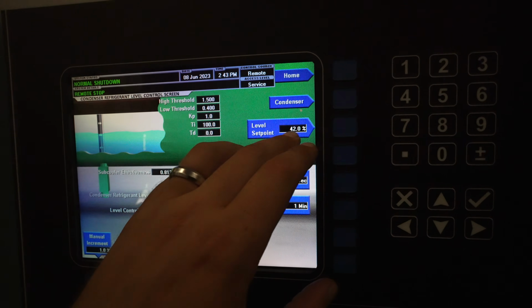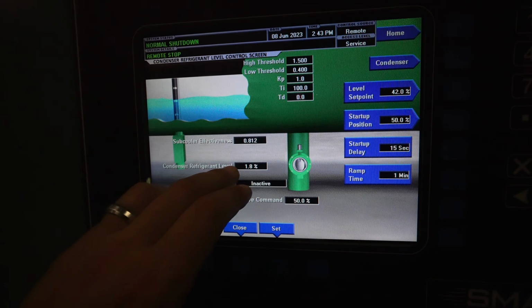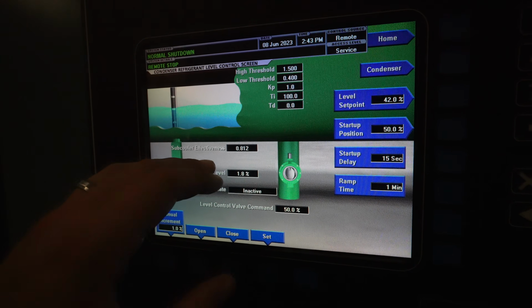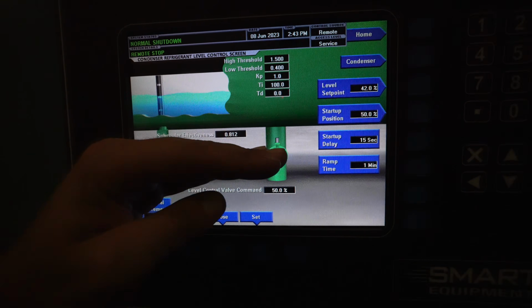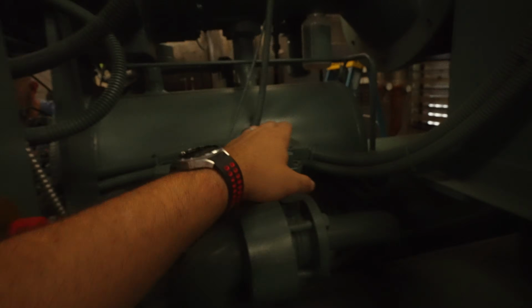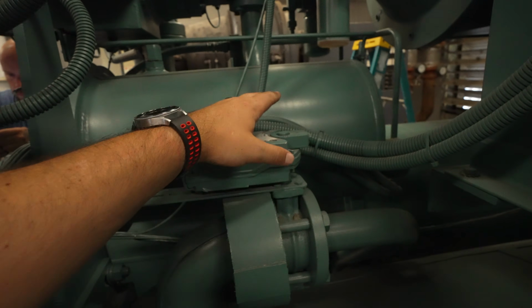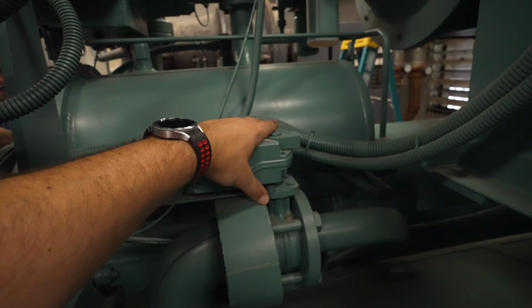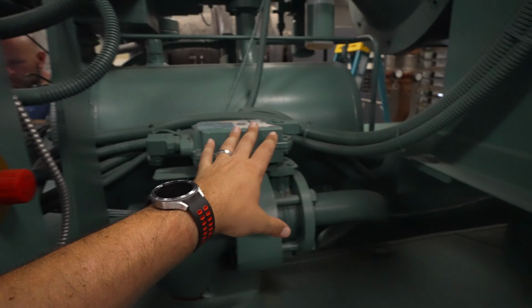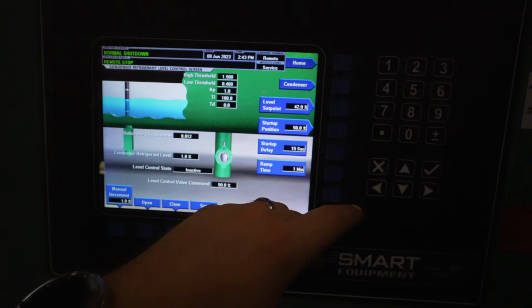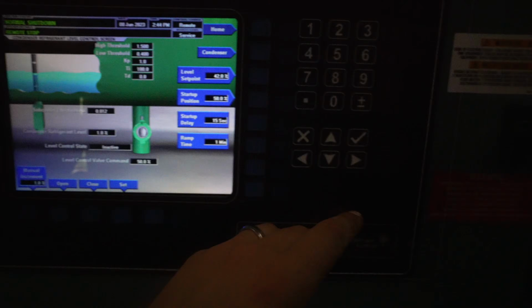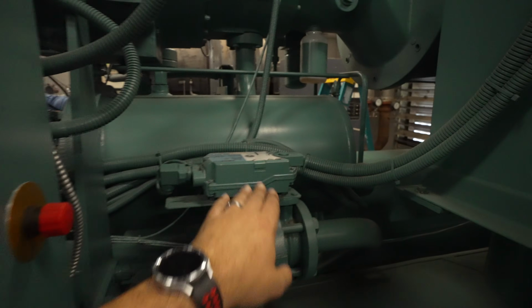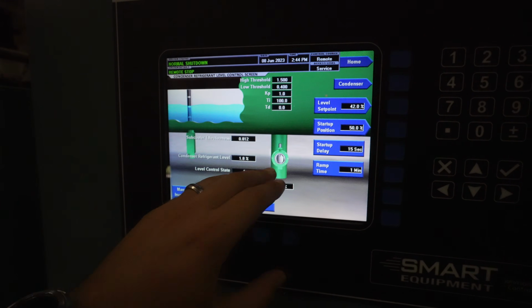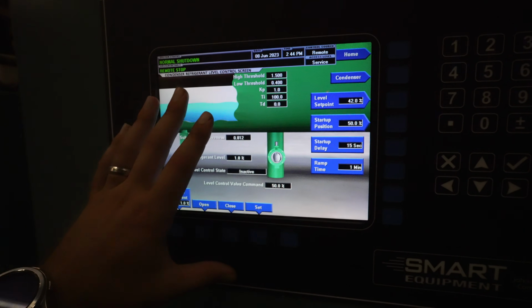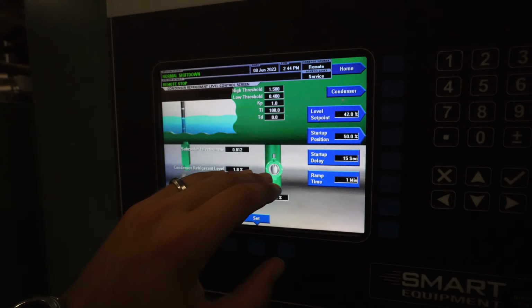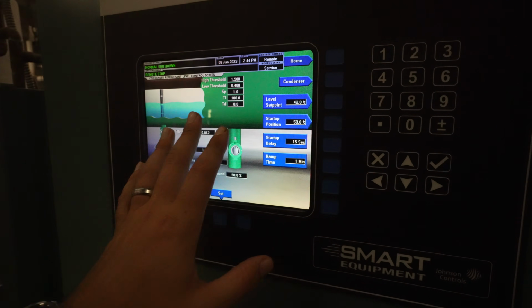And so what you do is, as you slowly adjust this, you let the condenser liquid level balance itself back out, and when it stabilizes again, because we've got to start controlling that, how it's doing that is backing down on this valve, which is backing up more refrigerant into the condenser, and then that level, that percentage in the condenser, is telling this valve whether to open or close. So as it was doing that, we eventually got to where we were able to level off at our 42% constant level.